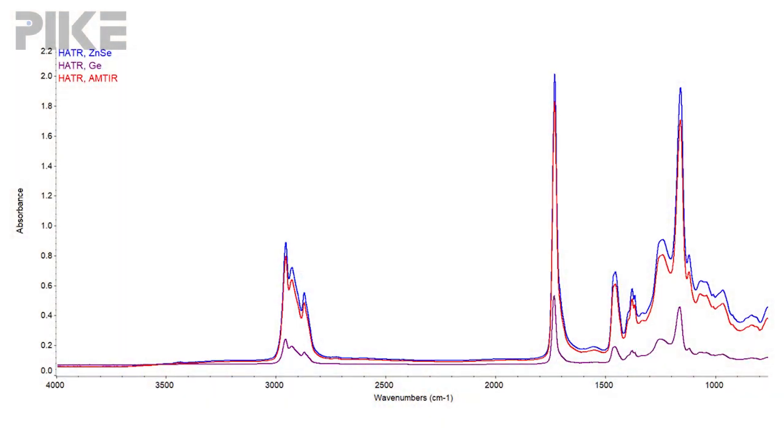Alternatively, we offer an AMTIR crystal. AMTIR and zinc selenide are more similar in refractive index, so you're really not going to give up much sensitivity with an AMTIR crystal, but you can test that acid. Thanks for watching this week and we'll see you next time.